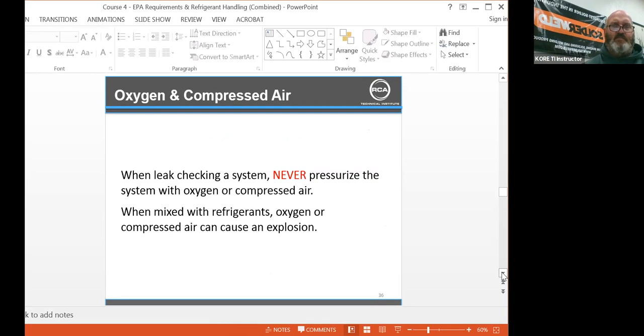When leak checking the system, never pressurize the system with oxygen or compressed air. When mixed with refrigerant, oxygen or compressed air can cause an explosion. If you go on YouTube, there is a video out there that I saw a couple weeks ago of a guy pressure testing with oxygen on a VRF. I think it was in India, and it blew him apart. It was a horrible video to see, but they used oxygen to leak test a VRF, a little ductless split, and my gosh, it was horrific. So we don't want anything like that to happen to you guys.